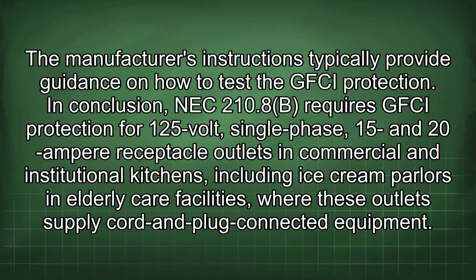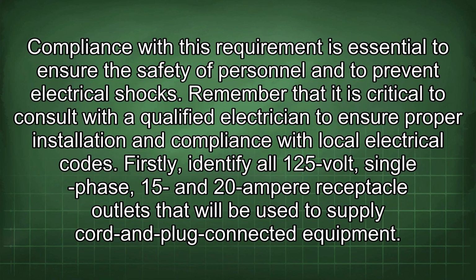In conclusion, NEC 210.8b requires GFCI protection for 125-volt single-phase, 15 and 20 ampere receptacle outlets in commercial and institutional kitchens, including ice cream parlors and elderly care facilities where these outlets supply cord and plug-connected equipment. Compliance with this requirement is essential to ensure the safety of personnel and to prevent electrical shocks. Remember that it is critical to consult with a qualified electrician to ensure proper installation and compliance with local electrical codes.